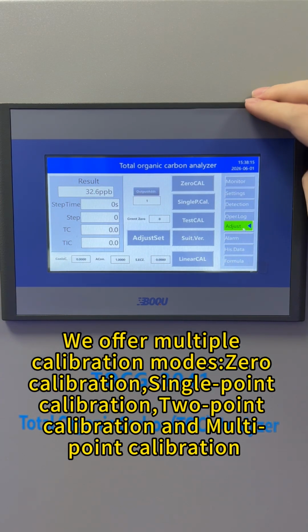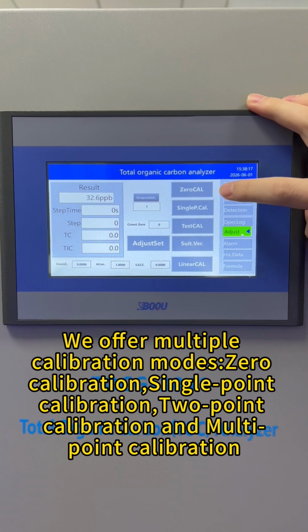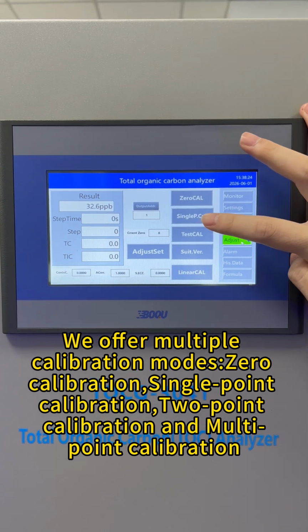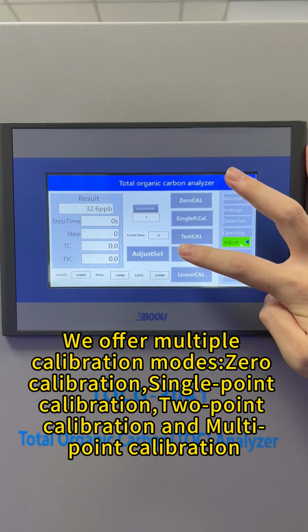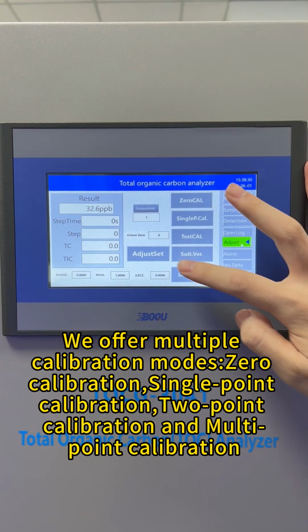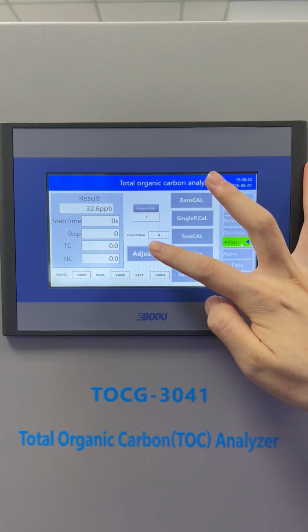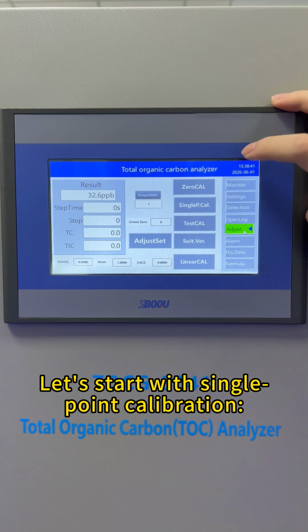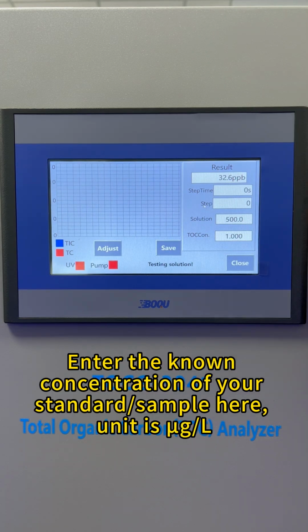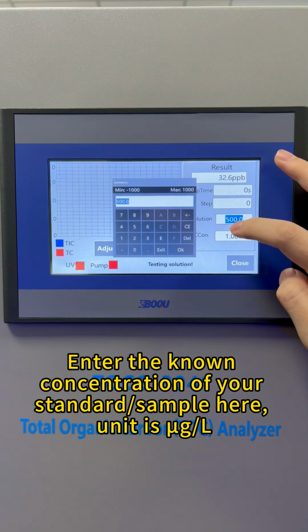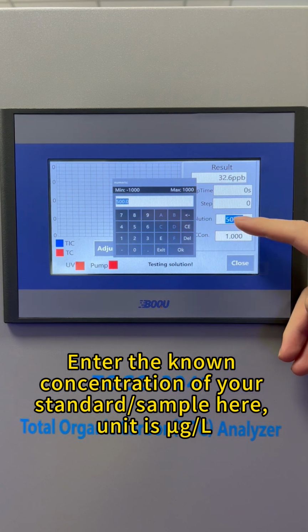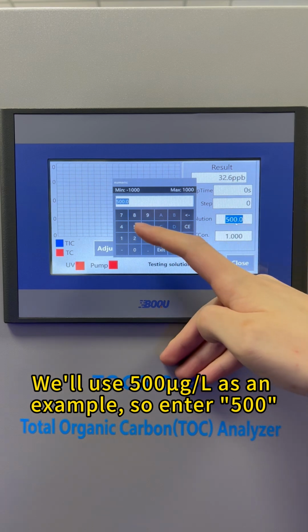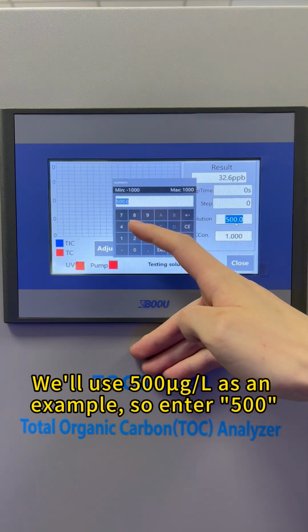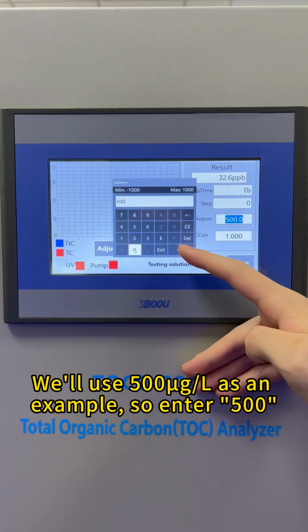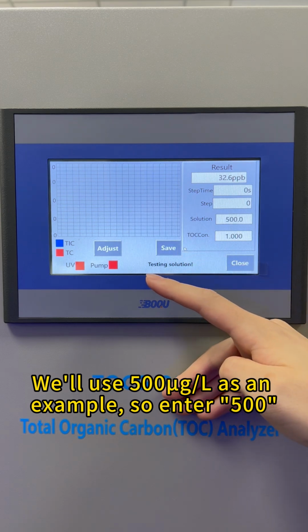We offer multiple calibration modes: 0 calibration, single point calibration, 2-point calibration, and multi-point calibration. Let's start with single point calibration. Enter the known concentration of your standard sample here. The unit is micrograms per liter. We'll use 500 micrograms per liter as an example, so enter 500.